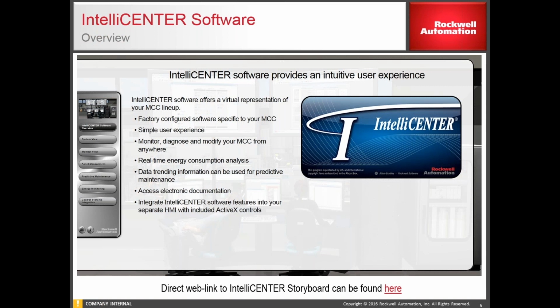So again, with IntelliCENTER software, it's a virtual representation of your MCC. So if you order an intelligent motor control center, the factory is going to create a data disk for that MCC. So that elevation of the MCC, specific to your order, you're going to have access to it from a remote location. So you install the software on your laptop, or if you have an HMI, you can drop the configuration right into an existing HMI so that you can monitor what's going on within that MCC. And again, it's factory configured. It's very simple to use.